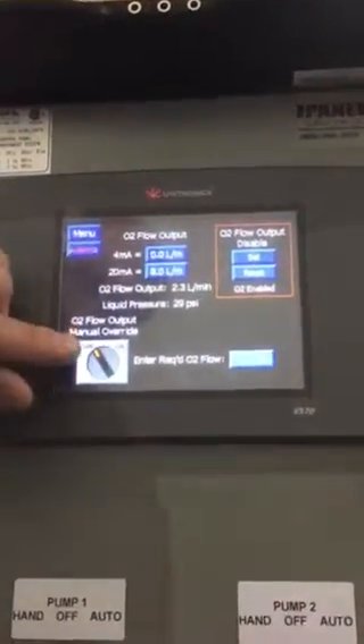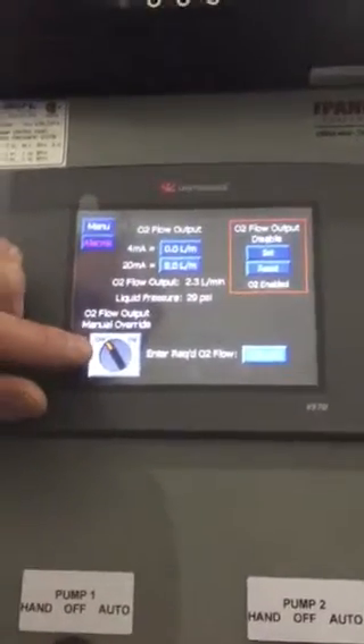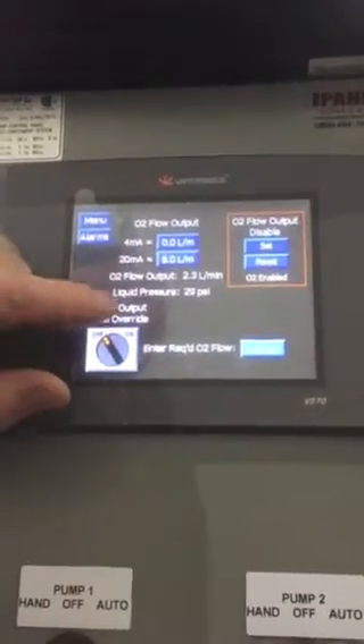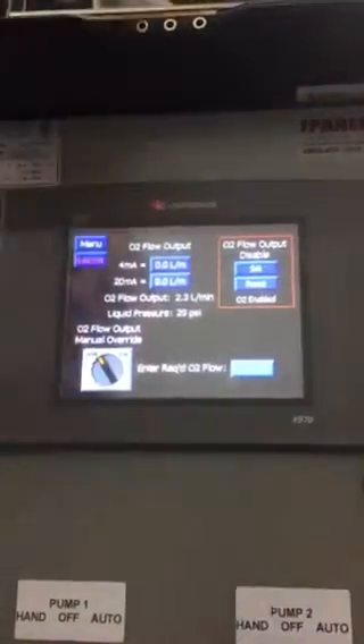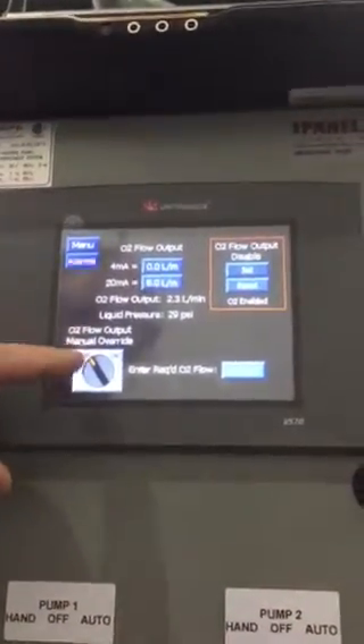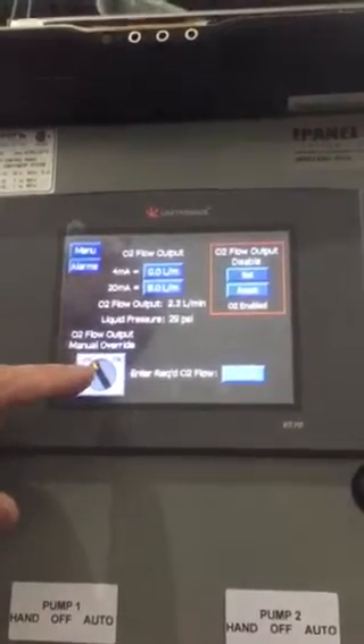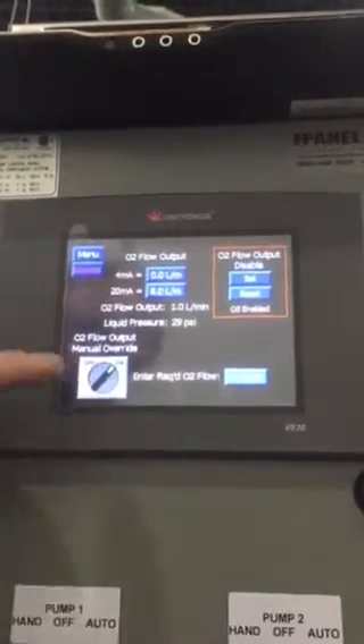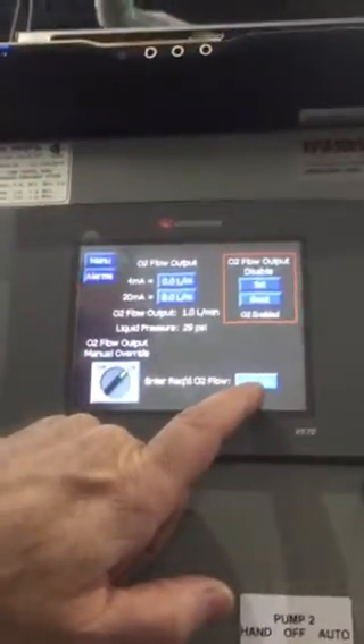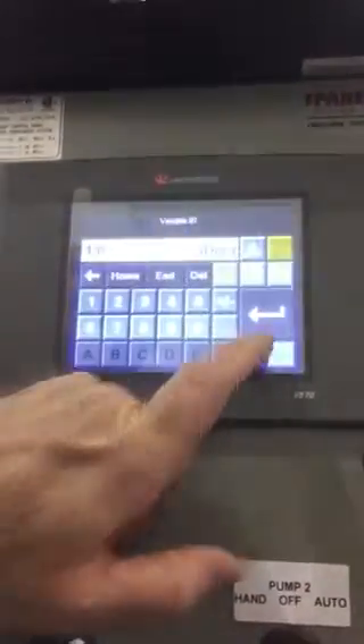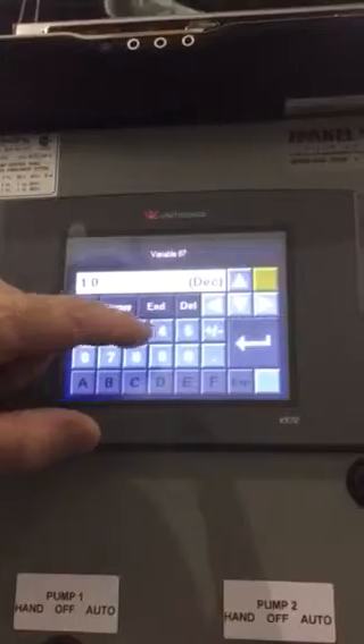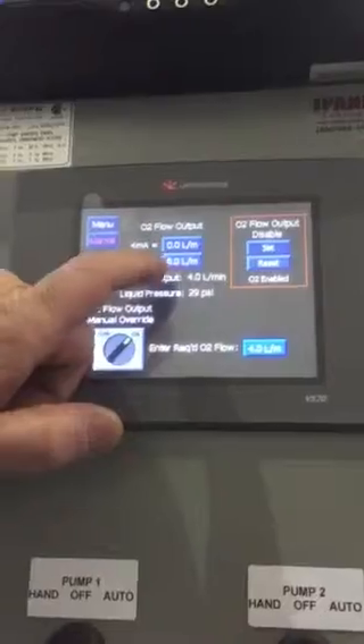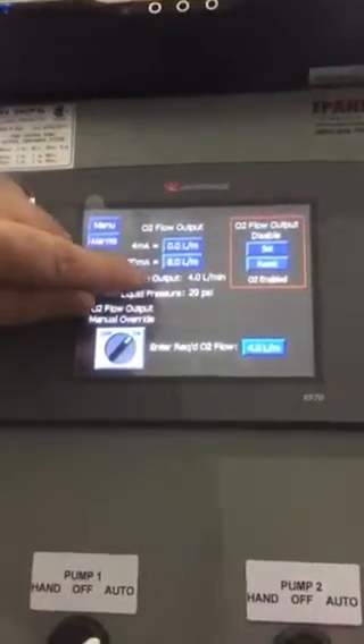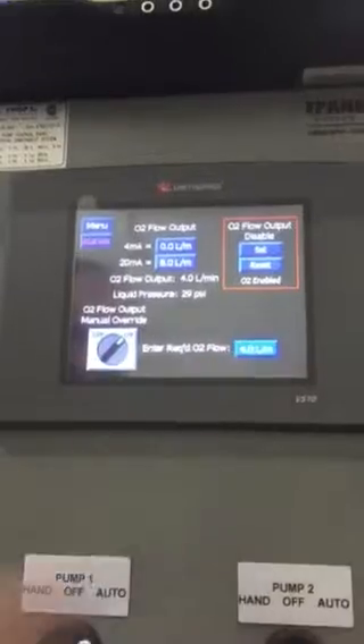Now, if you decide that for whatever reason, we want to put more oxygen flow into the unit, we can override it using this O2 flow output manual override. That can be done remotely on the laptop also, or it can be done manually here. So when I push the switch on, the flow rate of oxygen should drop to 1 liter per minute, which it did. If you want to go in and change that, say you want to put it to 4 liters per minute, you just type in 4, hit enter, and now we're flowing it at 4 liters per minute at this pressure. Oxygen flow output 4 liters per minute, set at 4 liters.